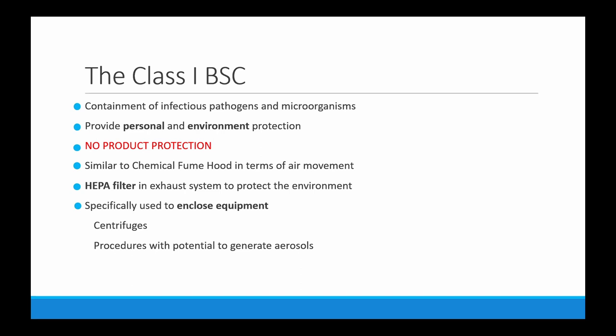The common feature of all three classes of biosafety cabinets is that they are used for the containment of infectious pathogens and microorganisms that can pose a threat to lab workers and the external environment. Class one biosafety cabinets provide only personal and environmental protection, and no product protection.